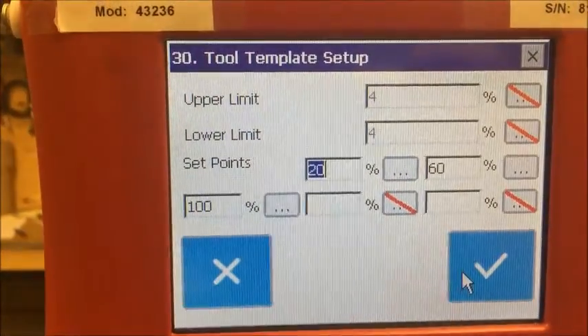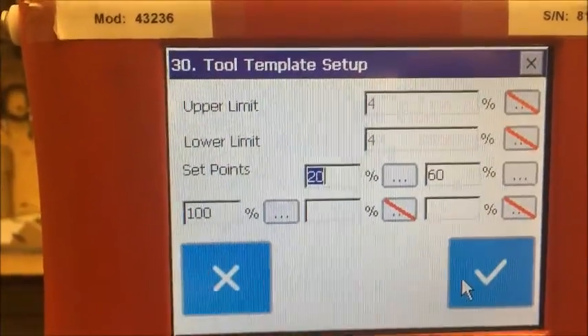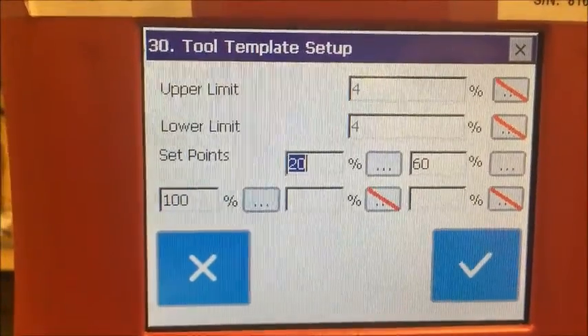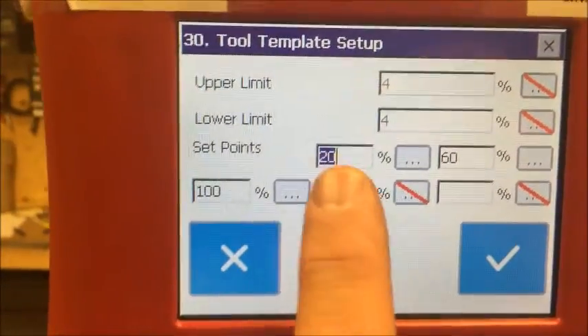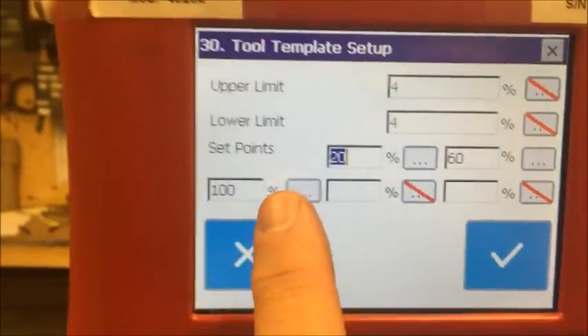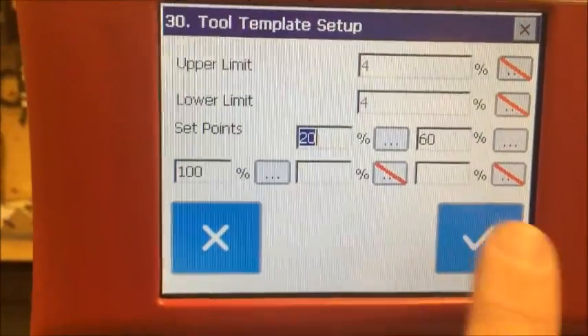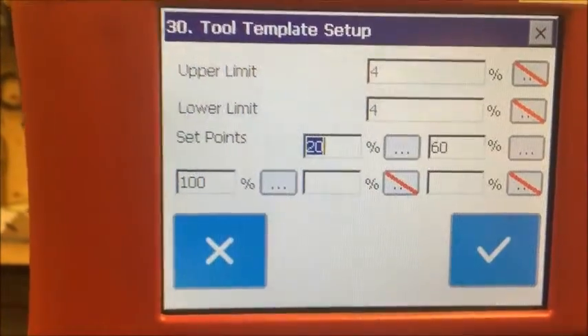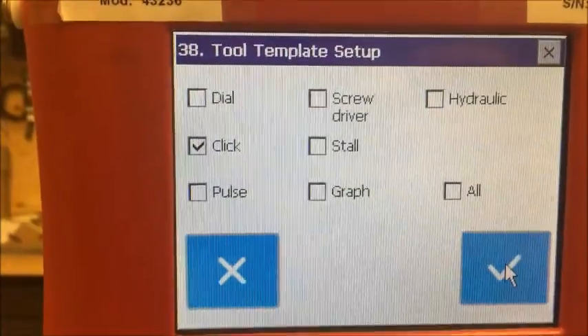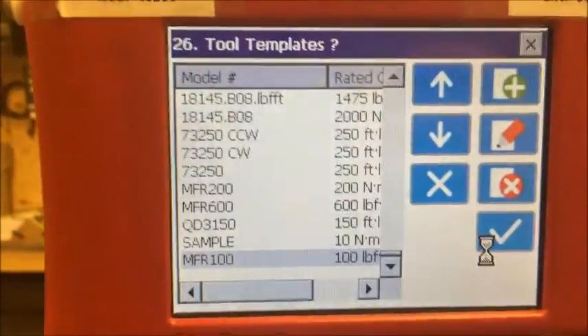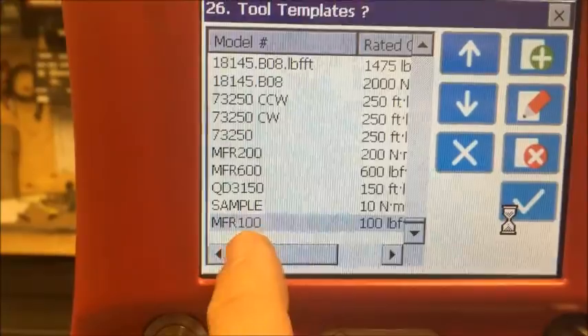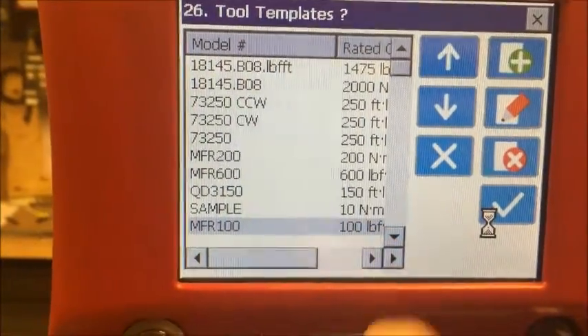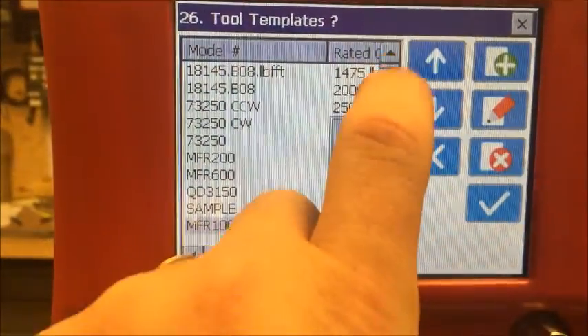These are our set points. Our upper limits are 4% and lower limits are 4%. That's what we consider to be good pass and fail, I guess. We want to check the wrench at 20, 60, and 100, which is pretty normal. You can actually check it at 5 positions if you wish. And it is a click style wrench. Now it's in our list of tools. Our MFR 100 is a 100 inch-pound wrench, which is at the bottom here now.